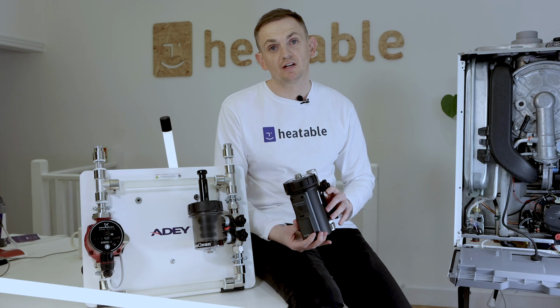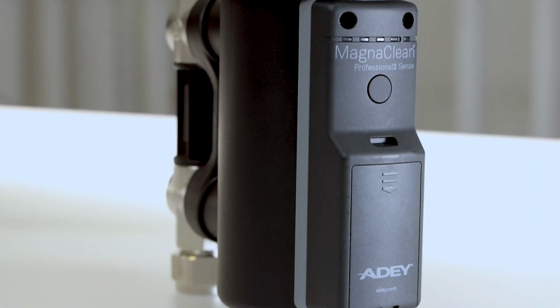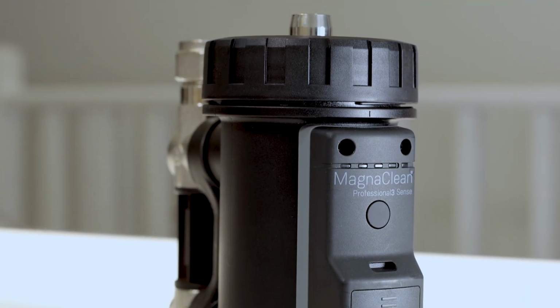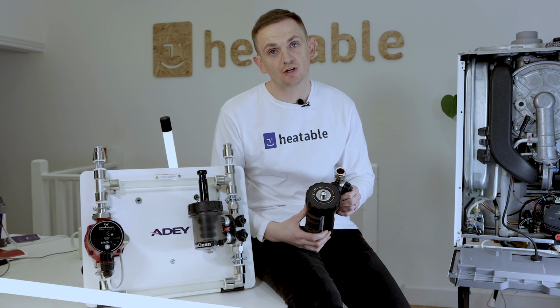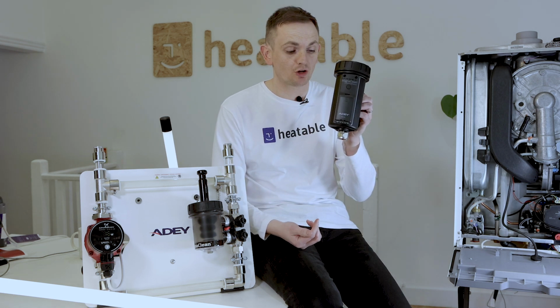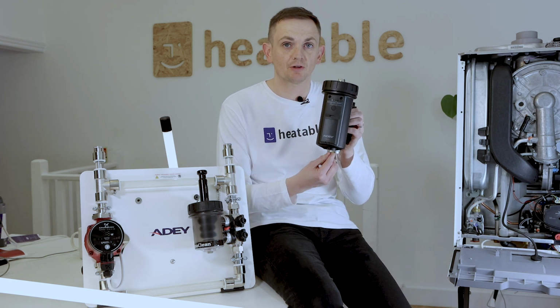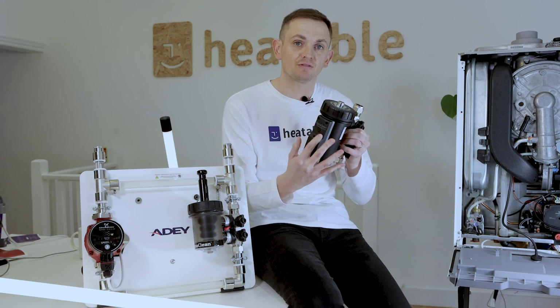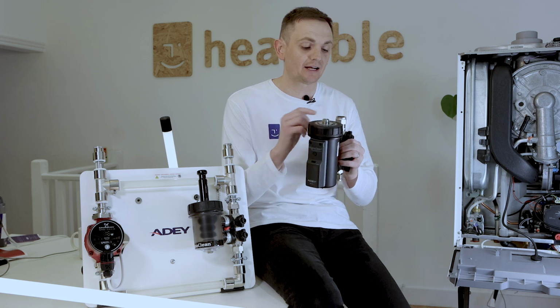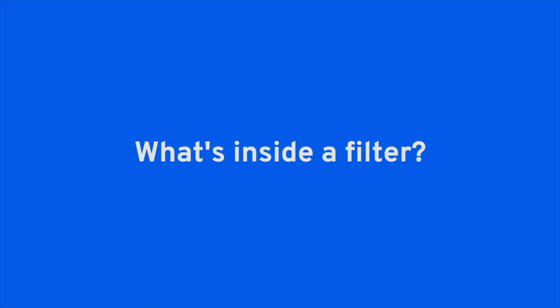So a boiler filter is a device which captures magnetite, which is the leading cause of most boiler breakdowns in the UK. And a boiler filter works by having the heating water return into the system at the bottom of the valve, enter the filter, the magnet captures the material, and clean water leaves the system.